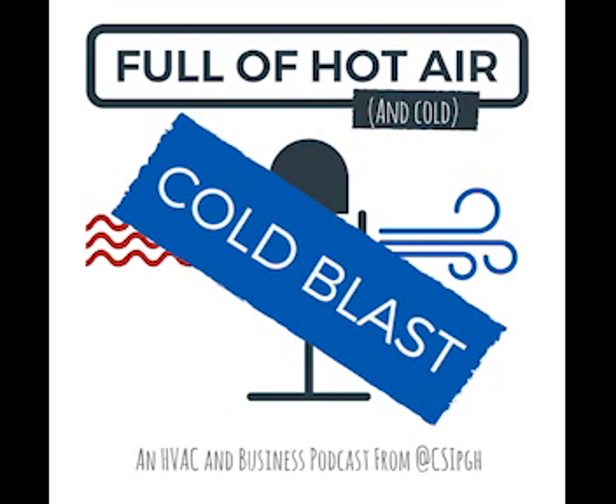I want to eliminate everything to do with the outdoor unit. So this is basically the outdoor unit with no wires connecting to the indoor unit whatsoever. You could leave S1 on there or take it off; it doesn't matter either way. Then I'm going to have them take the reading there. Now, if I read 24 volts DC, that's what the voltage should read, not fluctuating, because remember, it only fluctuates when we're communicating.